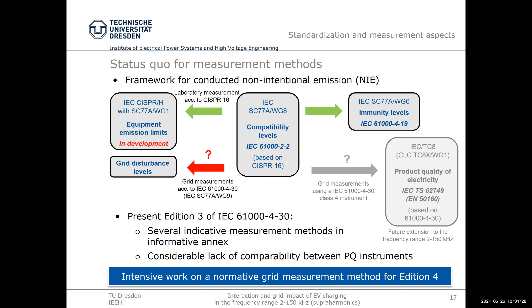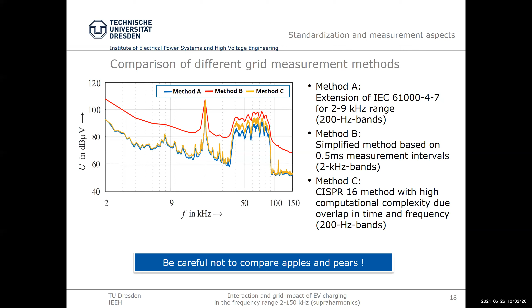Just to give you an idea of how different they are, here is a comparison of the 3 methods that are provided in 61000-4-30. Particularly for emission that is not narrowband emission, in this frequency range you can see significant differences between the methods. If you have a rather small emission, they usually provide similar results, but you should definitely be careful if you carry out such measurements to double check which method has been implemented by the manufacturer, in order not to compare apples and pears, particularly if a second instrument is installed which might use a different method.